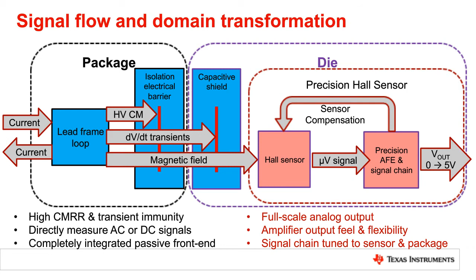So those key benefits kind of map to 2 really specific applications, right? One is for measuring inline PWM signals in things like inverters that might drive an inductive load like a motor, or are generating a 60 hertz AC output through a filter. And the benefit here is that high common mode rejection and CMTI eliminates coupling from the PWM voltage transients into your signal chain. So you don't have to worry as much about sampling coherency and trying to catch a specific point in a PWM.